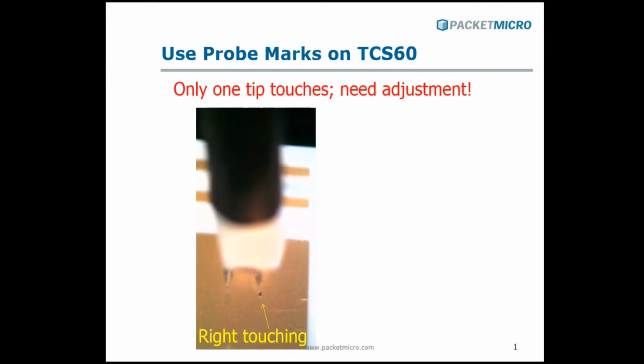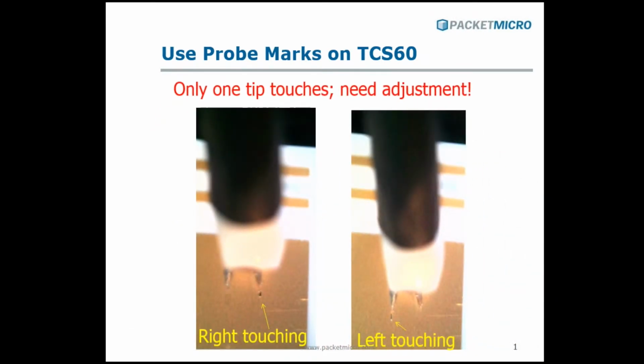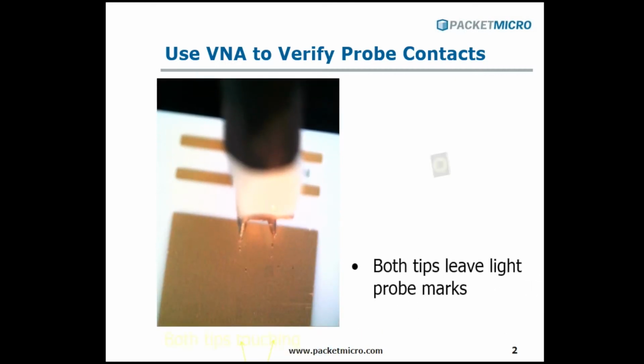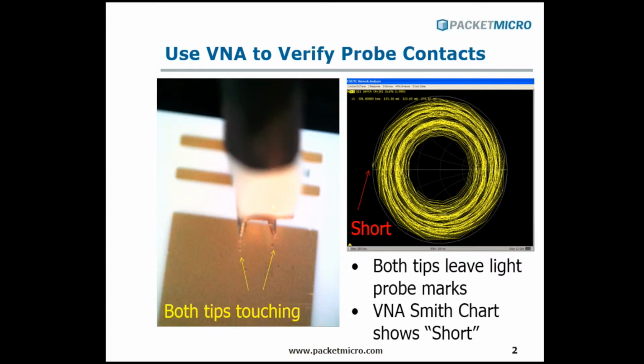You can also use the TCS60 substrate to perform the probe tip planarization by observing the probe scratch marks on the substrate. If you only see one tip mark, this means that only one probe tip is touching down, so planarization adjustment is needed. The two probe tips are properly leveled when you see two tip marks on the substrate while lowering down the probe with a TP60 or TP300 probe positioner. You can also use the Smith chart on the VNA to verify both tips are making good electrical contacts.